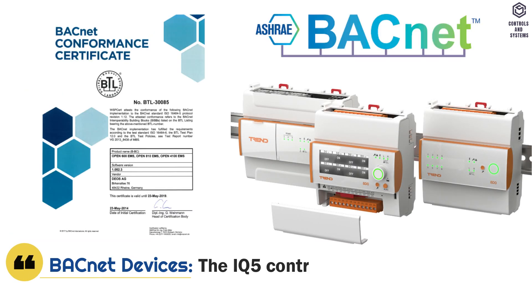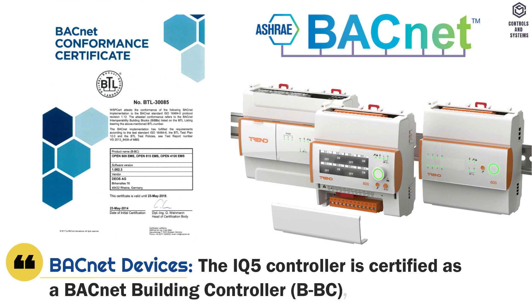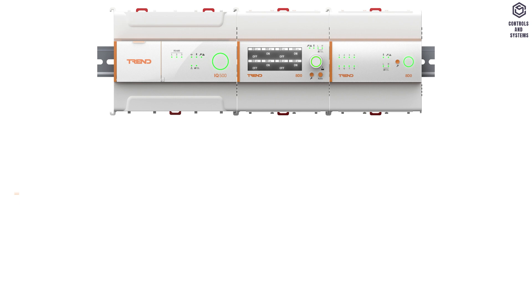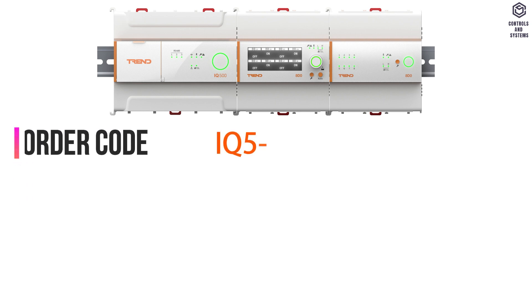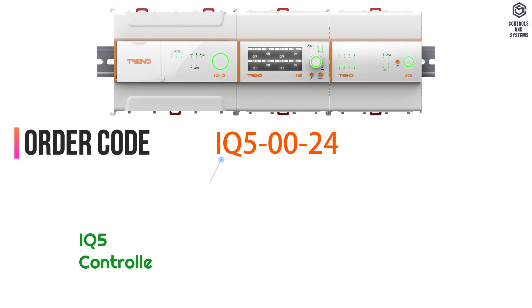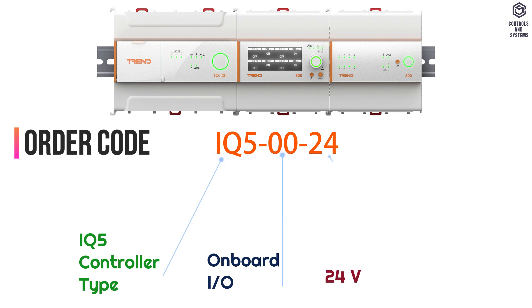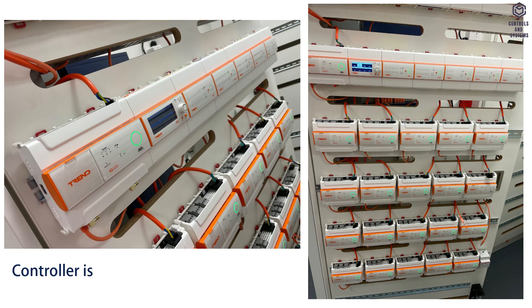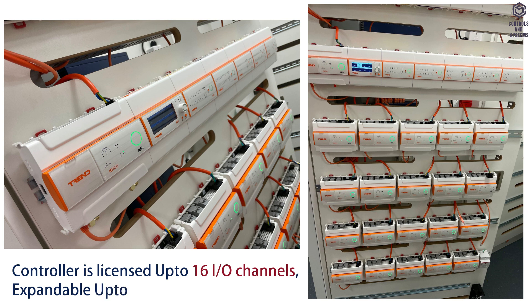BACnet Devices: the IQ5 controller is certified as a BACnet building controller. Licenses — controller order code is IQ5-00-24, where IQ5 means controller type, 00 means onboard inputs and outputs, and 24 means controller power supply. The controller is licensed up to 16 inputs and outputs channels and is expandable up to 500 inputs and outputs channels.